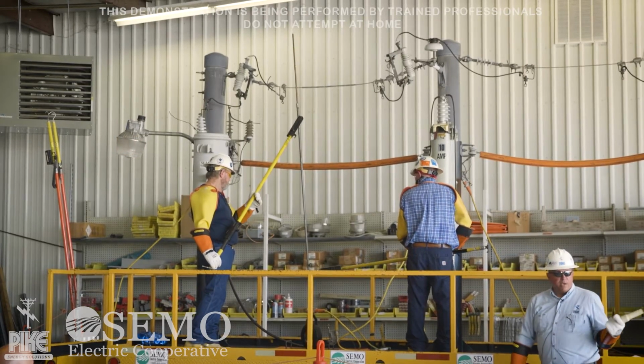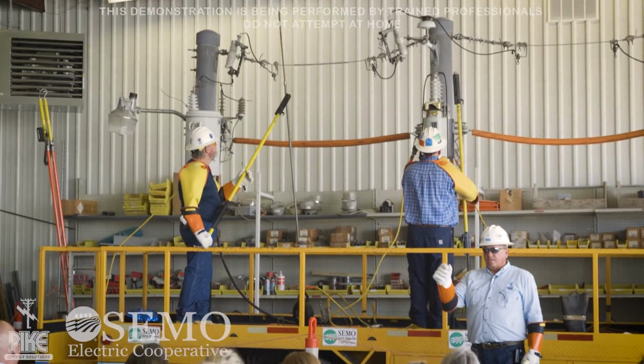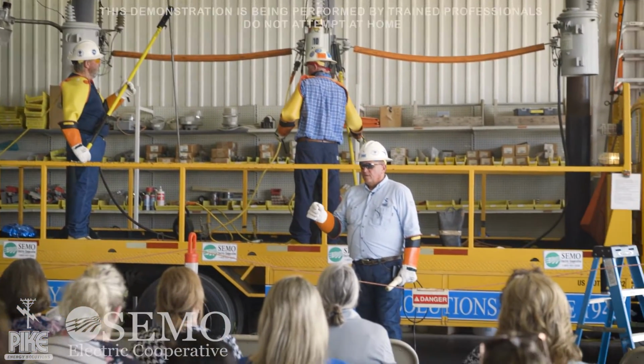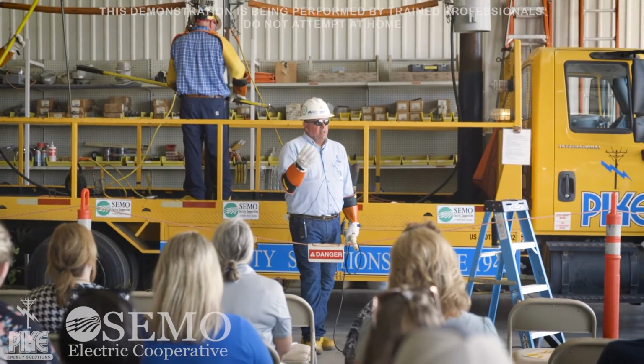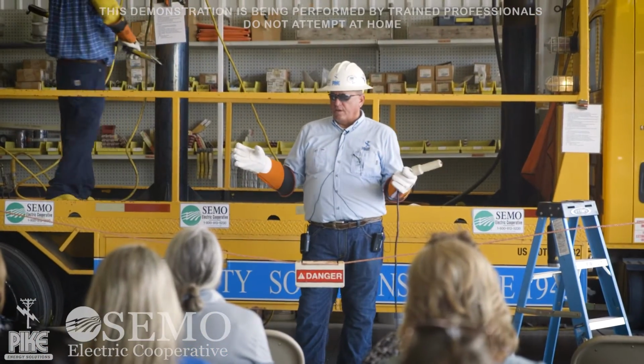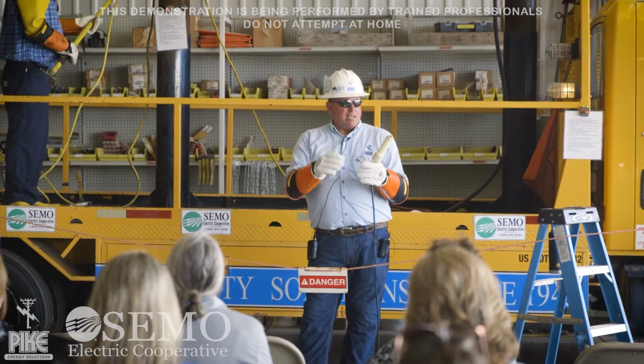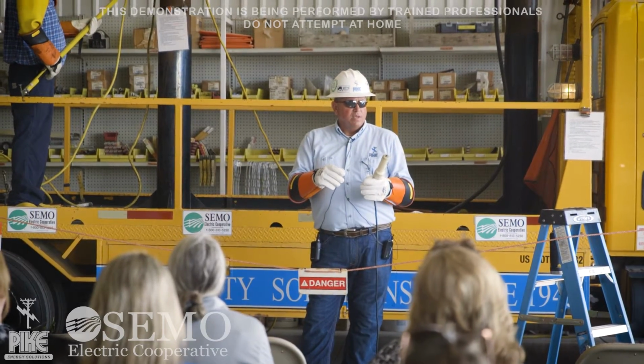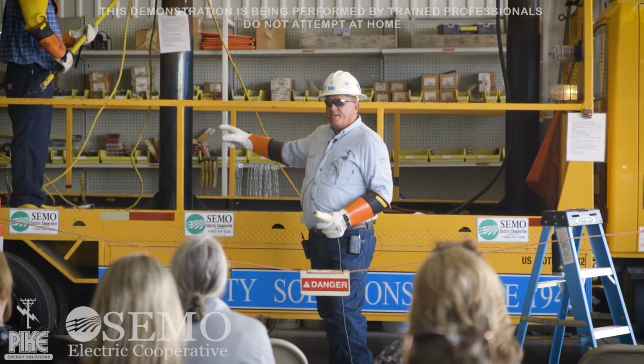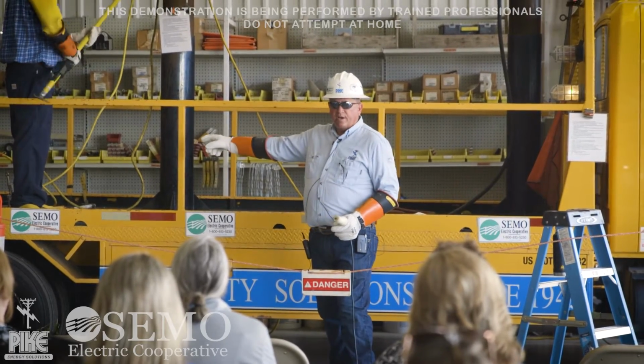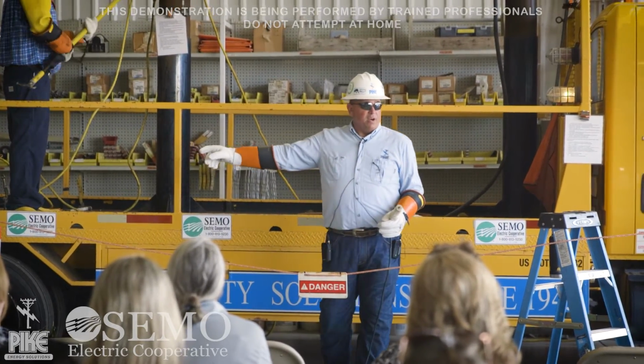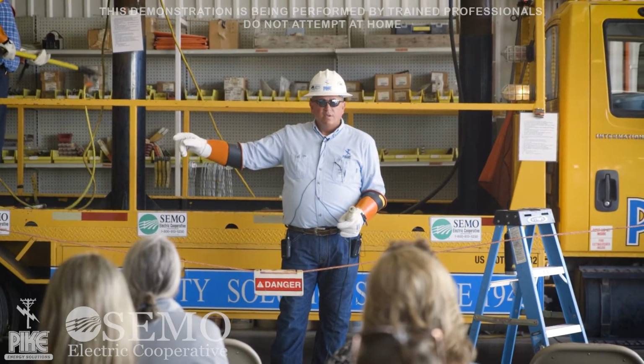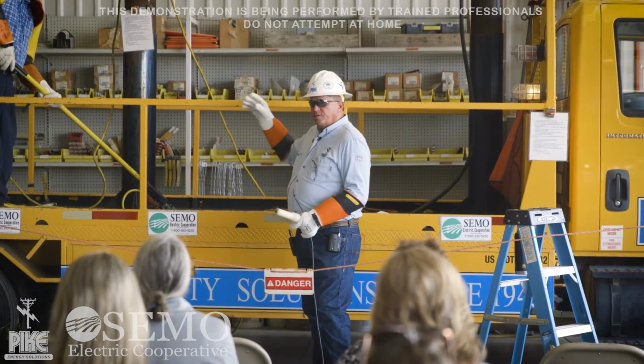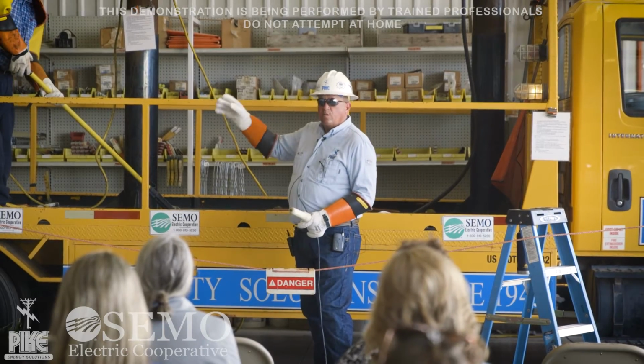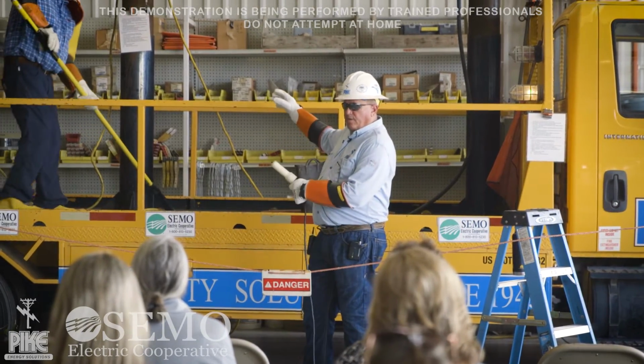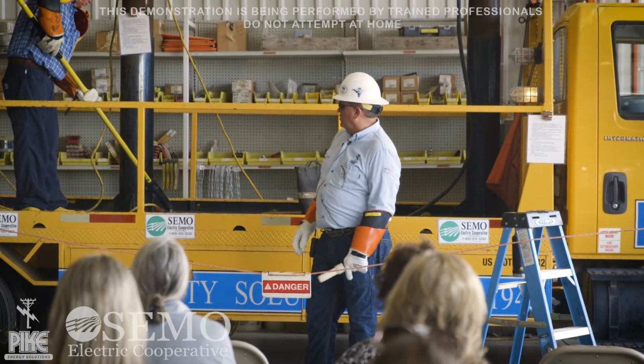I actually call it a myth. A lot of people think electricity will seek the closest path to ground. Well, that's true, but it's not 100% true. It'll seek all paths to ground, but it will take the very best direct path to ground. In other words, if we could check the bottom of that wheel right there, I'd imagine there's a little bit of energy still on it. But we gave it a better path, took it away from the ground and took it straight back to earth. That's the reason we ground.